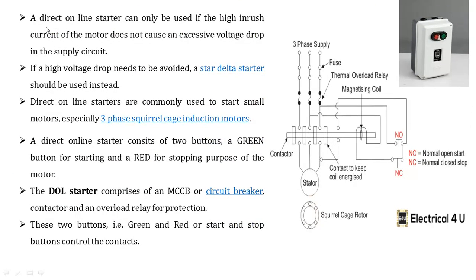A direct online starter can be used if the high inrush current of the motor does not cause an excessive voltage drop in the supply circuit. If the high voltage drop needs to be avoided, a star delta starter should be used. This is another starter which is required to start the three-phase induction motor. The direct online starters are commonly used to start small motors. Basically, this DOL starter is used to start small motors, especially a three-phase squirrel cage induction motor.